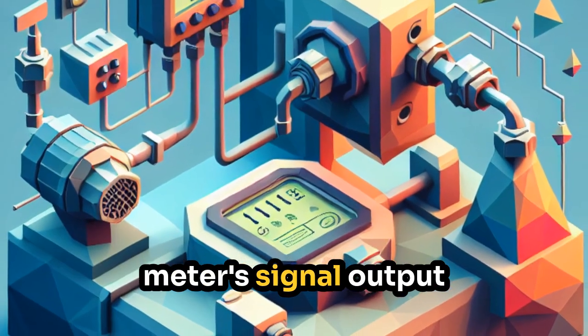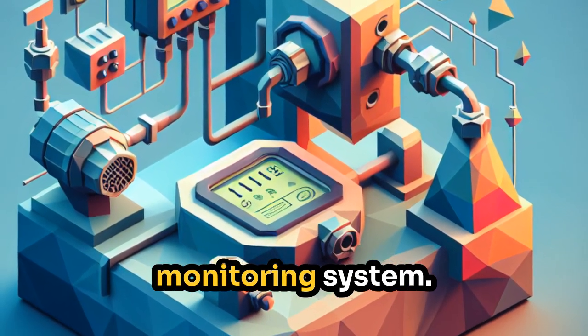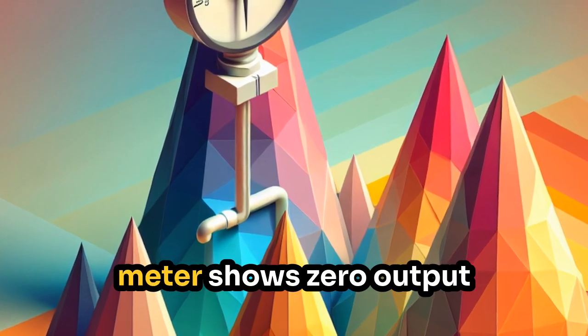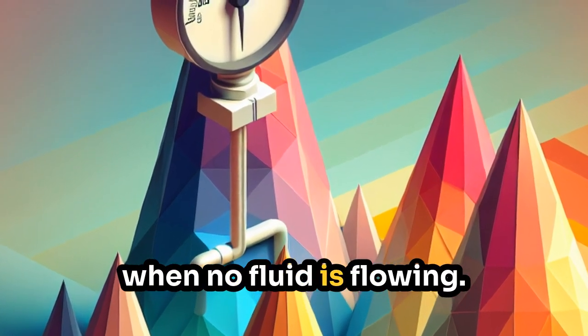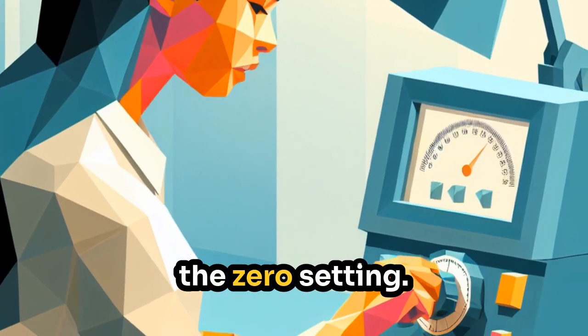Connect the flow meter's signal output to the calibration monitoring system. Verify that the flow meter shows zero output when no fluid is flowing. If necessary, adjust the zero setting.